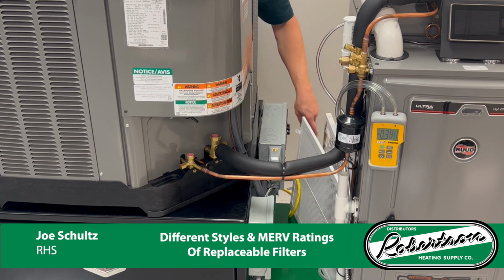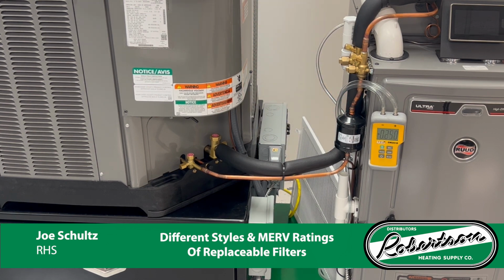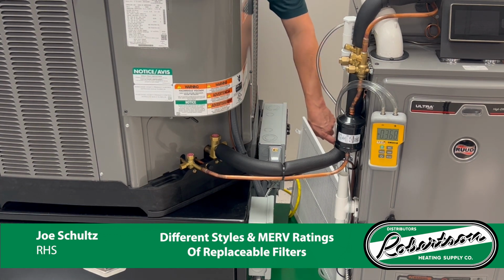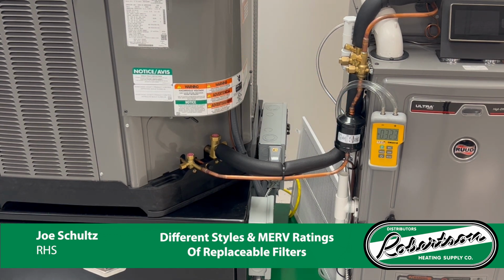So the next filter that I have is a Merv 8 filter. So these are all pleated. So you can see our static pressure is hovering right around 0.37 approximately for that Merv 8 filter. So we'll move up into a little bit higher Merv rated filter, which is our Merv 10 filter.